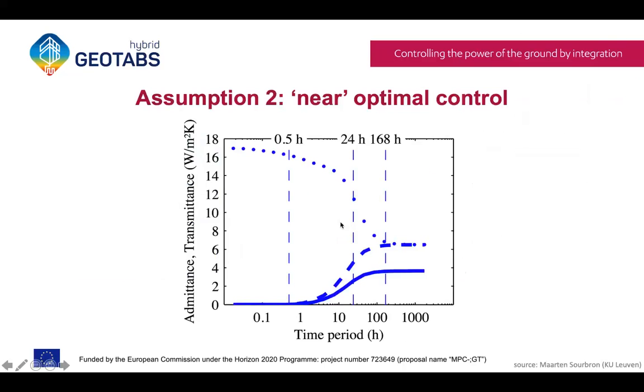As you can see in this graph, excitations that are too fast basically have no impact on the zone - 100% of it is attenuated - while very slow excitations are not affected by the thermal mass. The typical excitations we have in buildings, with a cycle or time period of a few hours to a day, are heavily affected by the thermal mass and therefore need to be predicted by a controller.